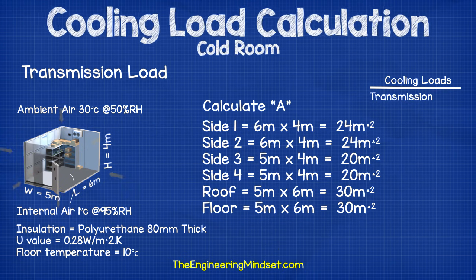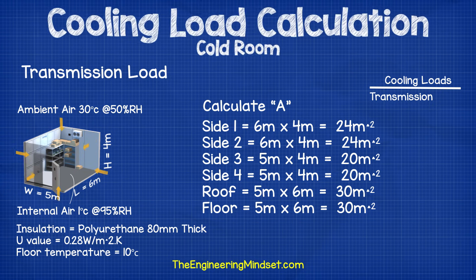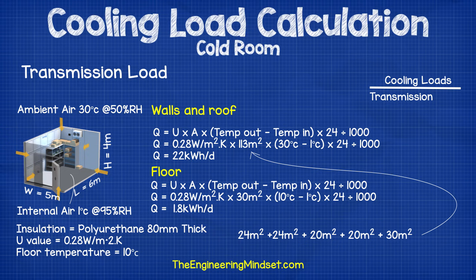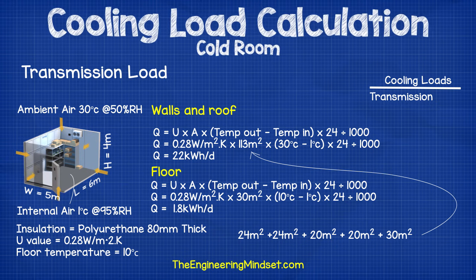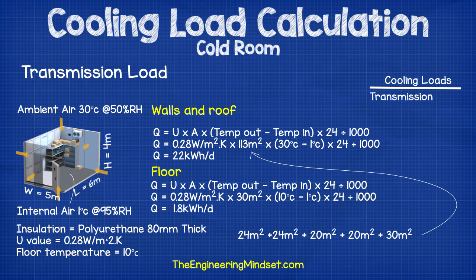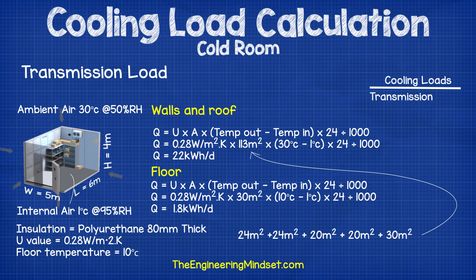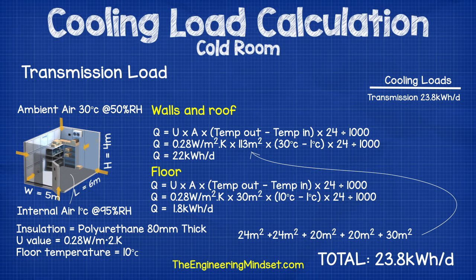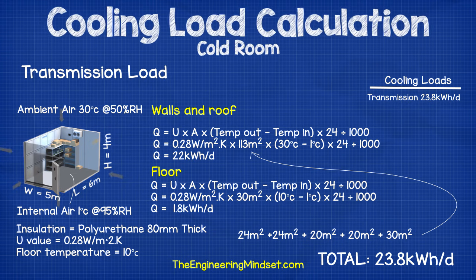To calculate the area A, it's just the size of each of the internal walls, so we drop the numbers in to find the area for each wall, the roof and the floor. You'll need to calculate the floor separately from the walls and the roof as the temperature difference is different under the floor, so the heat transfer will be different. If the floor isn't insulated then you will need to use a different formula based on empirical data. Combining the walls and the roof gives a daily heat gain of 22 kilowatt hours per day, and the floor comes to 1.8 kilowatt hours per day, giving a total transmission cooling load of 23.8 kilowatt hours per day.